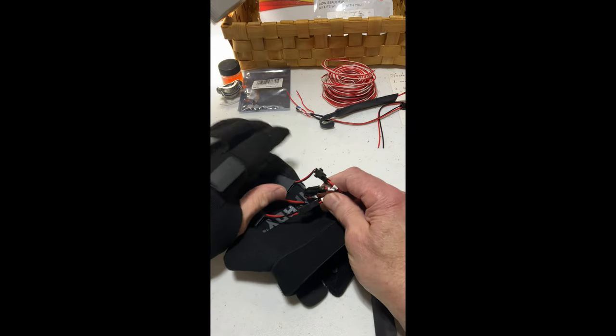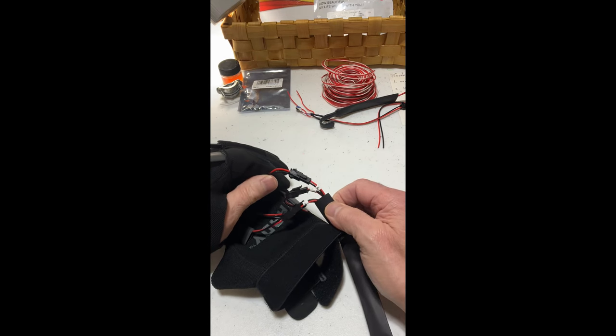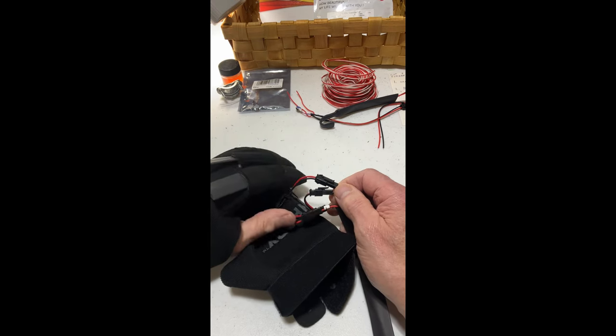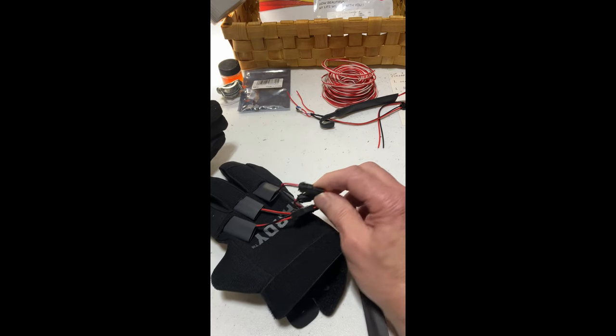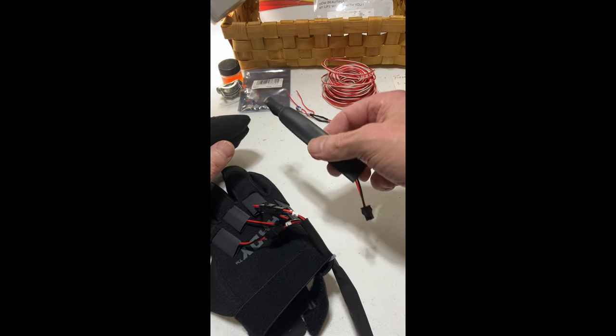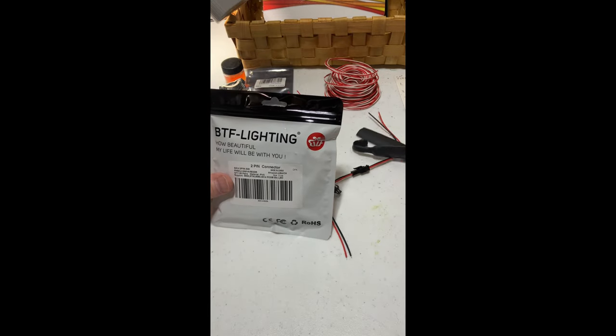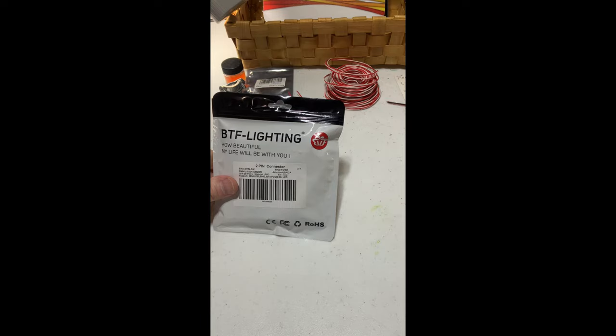I've got these little jacks — these are little disconnect jacks, numbered one through four according to your fingers. And if you have one that goes bad or stops working, you just unplug it and keep a bunch of spares on hand, replacing them as needed. The parts consist of LED lighting connectors, but they work perfectly for our application here.